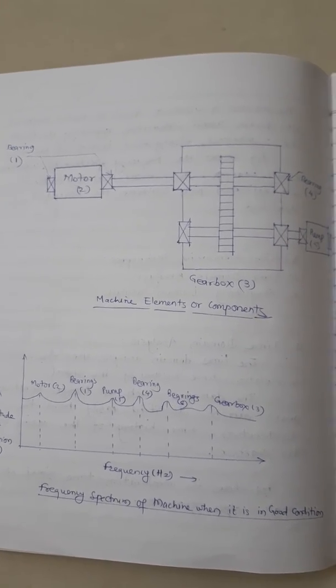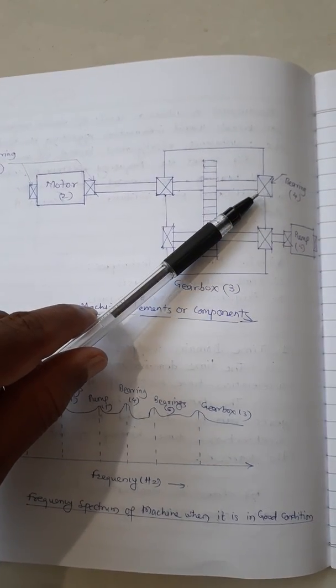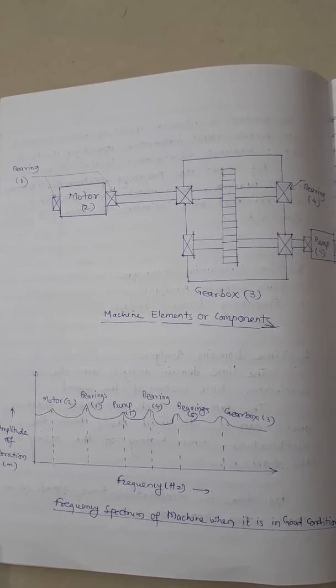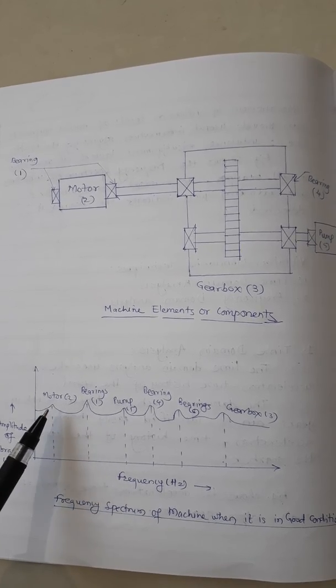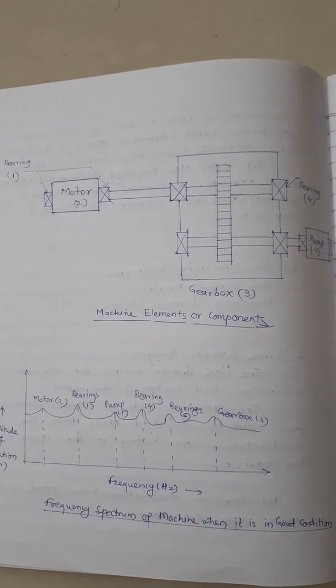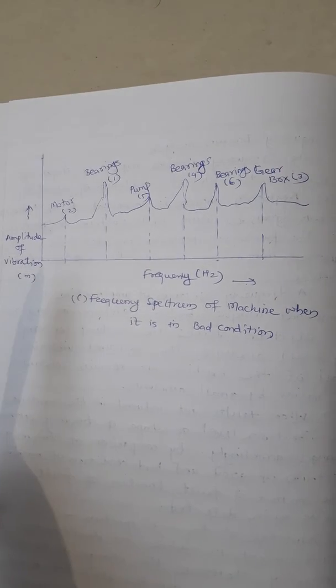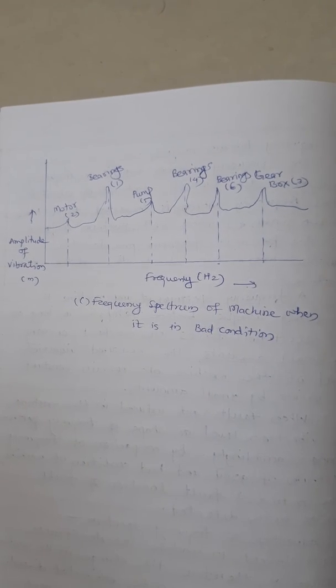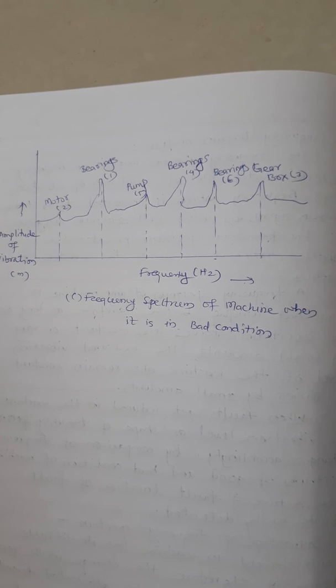For example, consider a machine with parts: motor, bearing, gearbox, pump, and other components, each having their own particular frequency. In the frequency spectrum plot when the machine is in good condition, each part like motor, bearing, pump, gearbox shows a particular vibration level at its frequency. When the machine is in bad condition, the amplitude of vibration at those particular frequencies increases. By comparing the two graphs, we can identify which machine condition has changed.